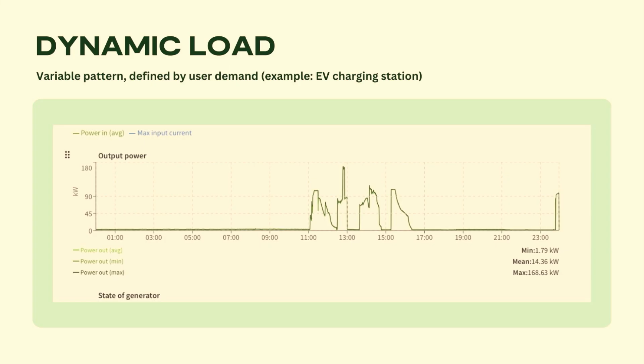As you can see in the bottom right corner, there's a very large difference between minimum and maximum capacity. Over this 24-hour window, the minimum is 1.8 kilowatts and the maximum is about 168 to 170 kilowatts, but on average that's only 14 kilowatts - that's a 32 amp plug. So we could have gotten enough energy from a very small grid connection to do this, basically just a CEE32 being used 24/7. In the middle there, that's the section where the cars are charging during the daytime - they come in, park up, whatever it might be.